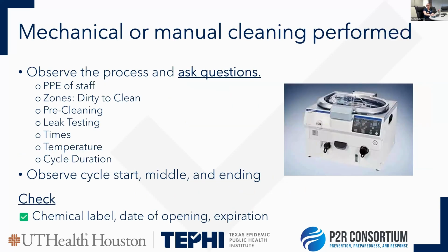Next, then you will start observing the high-level disinfection process. So we'll be looking at the pre-cleaning, the leak test, and kind of getting it ready if it's manually cleaning or if it's getting put in that AER, which you can see this is just one device. The devices look very different. Your facility might have one, you might have a ton of them. So making sure that you are observing how they're pre-cleaning it, how they're transporting it, what PPE is the staff wearing, are they changing PPE, is there designated dirty and clean zones within the suite? There should be a dirty sink and a clean sink, and how is that designated?